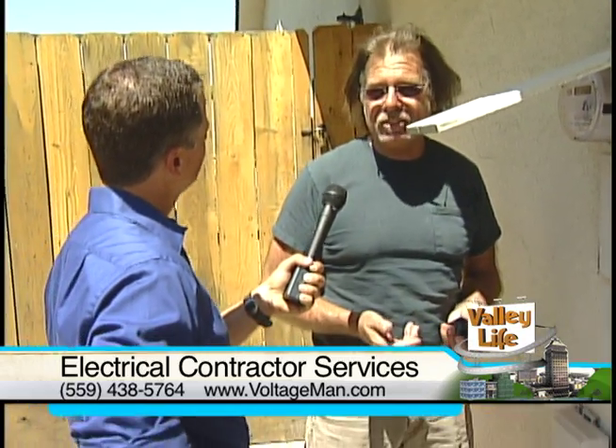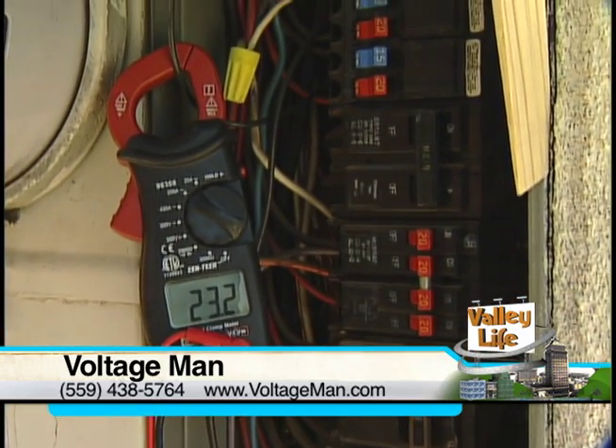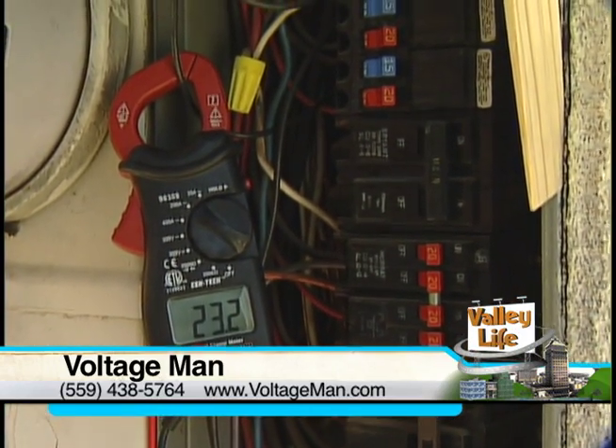And you know, a lot of people don't only plug in hair dryers, they got curling irons. And in the wintertime, they put in those little space heaters in the same thing. And these are designed just for 15 amps. And that's a small gauge wire. You could hear that thing start to heat up, sizzle, bam. Right. But it's not a bad breaker. The breaker's actually doing the job that it's supposed to do because it wants to turn off the power so that the wire doesn't heat up and start a fire like we did earlier.